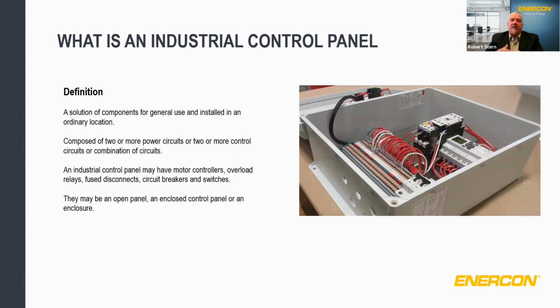An industrial control panel, by definition, is a solution of components for general use installed in an ordinary location. They're composed of two or more power circuits, two or more control circuits, or a combination thereof. An industrial control panel may have various items such as motor controllers, overload relays, PLCs, sensors, timers, fuse disconnects, circuit breakers, switches, terminal boards, etc. And they may consist of an open panel design, an enclosed panel, or just a bare enclosure itself. Next slide.